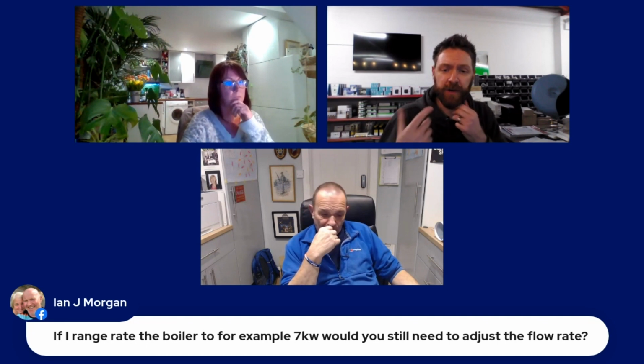So you still need to adjust that flow rate if you range rate it, because range rating doesn't necessarily mean that you're going to have the right amount of flow rate. It's a linear thing. If you think about a heat exchanger that's giving you 7 kilowatts of heat, you need the matching flow to get the 7 kilowatts of heat off that heat exchanger. If you have too much flow, you might actually not get that. You're not allowing that heat exchanger to get to the correct temperature.